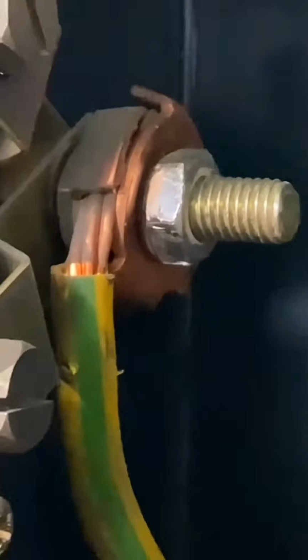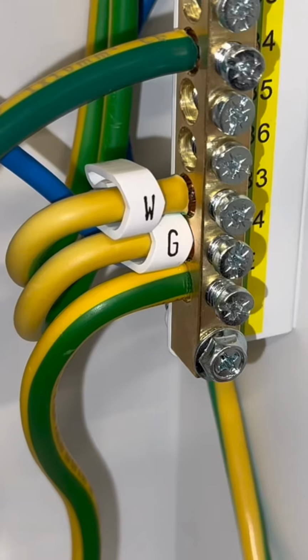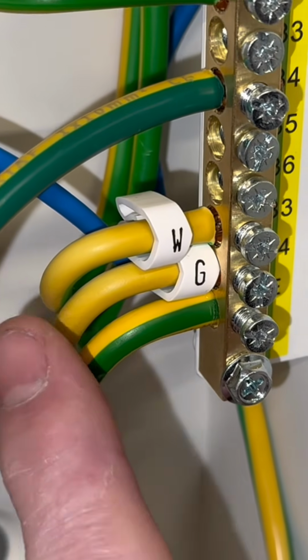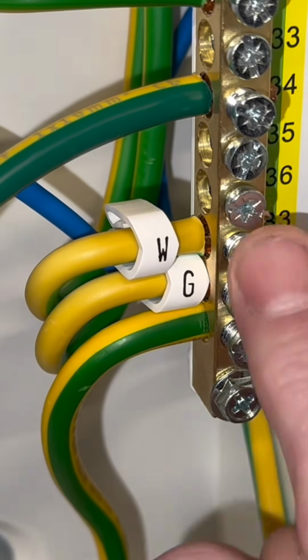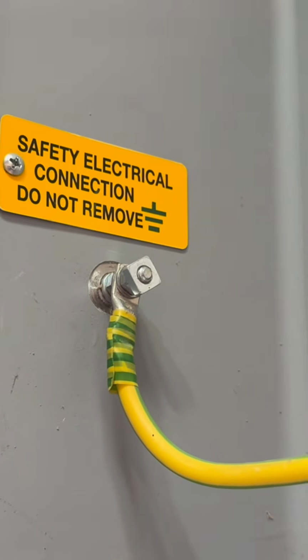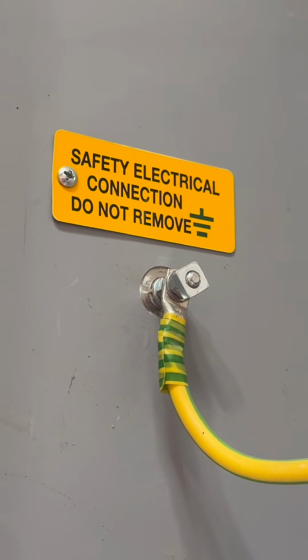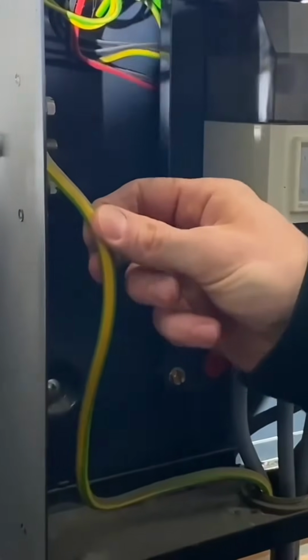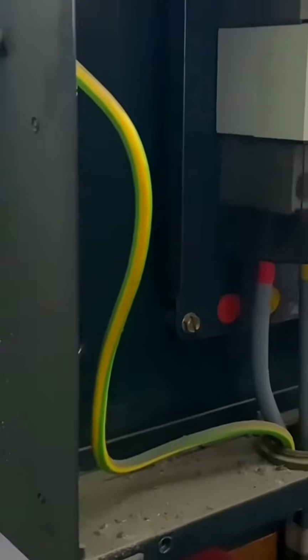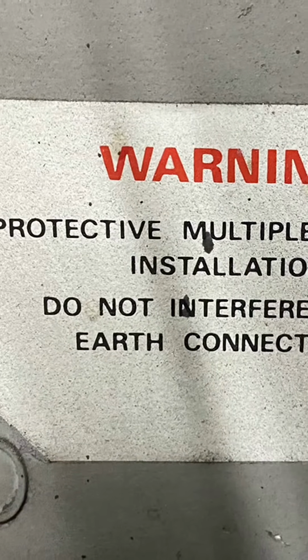So if we were not to disconnect it, then we'd have a problem with parallel earth paths via the extraneous conductive parts, through the bonding and stuff like that. So we want to know the external earth fault loop impedance, and so by removing this earth, that is just the external, nothing internal. Okay, and we've got an earthing system of TN-C-S. Yes. So what's the maximum reading for the external? On a PME or TN-C-S, it's 0.35 ohms.